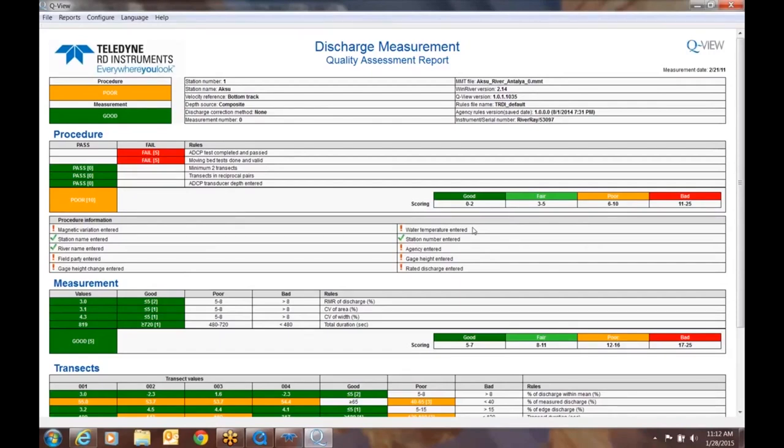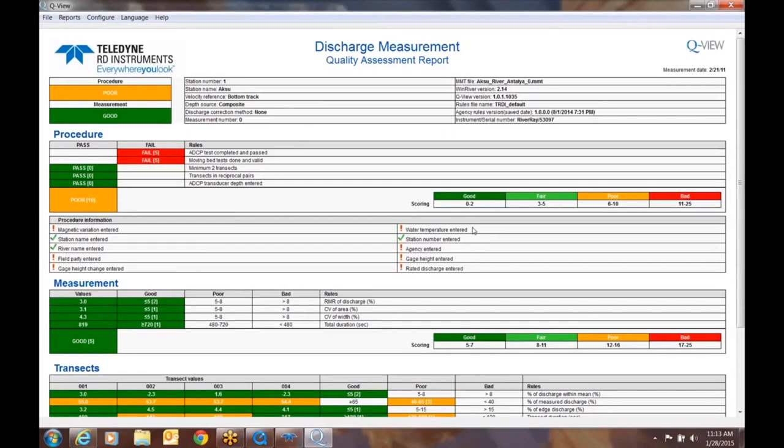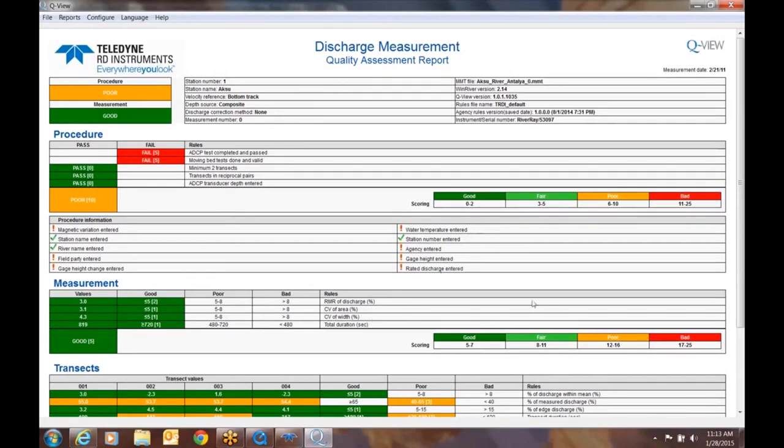Moving down from the procedure, let's look at the measurements. The measurements are looking good. The percent of the RMR of the discharge was fine, the CV of area and width, and the total duration, meaning did we take enough time to collect the transects? Again, in the rules wizard, which is something that we will cover in a later webinar, you have control over the weight of these, whether the rule is even going to apply to your data set. But right now we have this set at you need to do equal to or greater than 720 seconds to get a pass condition or to turn this into a green. So the measurement itself is good. It's got five points. And again, in this case, the lower the number of accumulated points, the better. So we're looking at a good measurement, although the procedure wasn't followed very well. The repeatability of the discharge measurements looked fairly good.